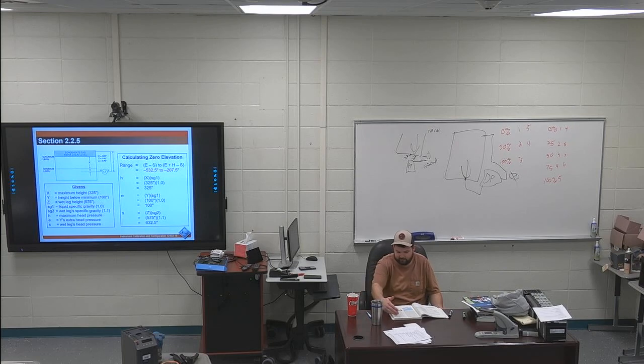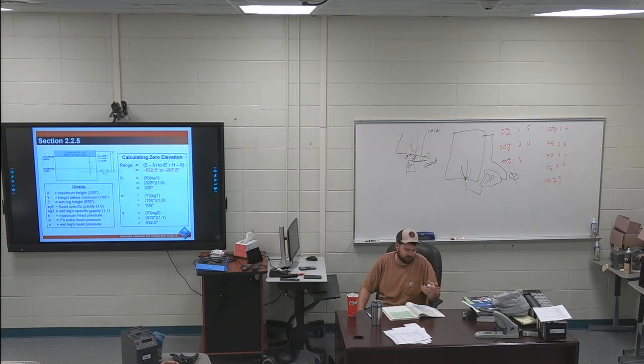But you can read through the steps, but you're going to do that 3 separate times in the last lab that you do for that trainer. I mean, it's easy because you're following step by step. It's 2 buttons. Page 18, 2.2.7. Temperature transmitters with analog outputs. Third paragraph, first sentence is highlighted. The 2 most common types of temperature sensing devices connected to a temperature transmitter are thermocouples and resistance temperature detectors, RTDs. That should sound familiar. RTDs and thermocouples, those are going to be your most common ways of sensing temperature.